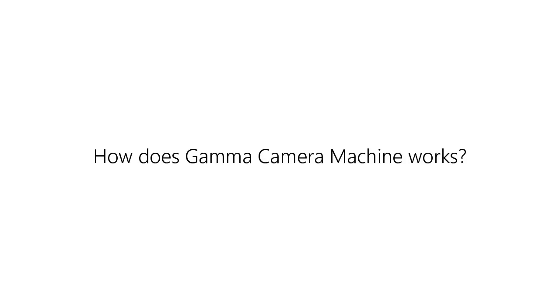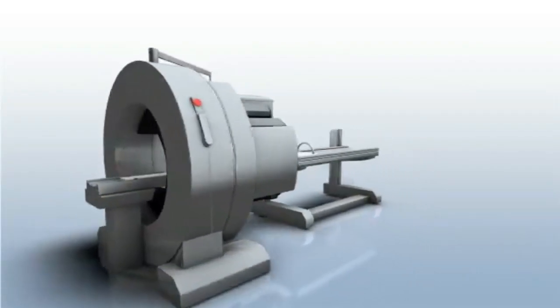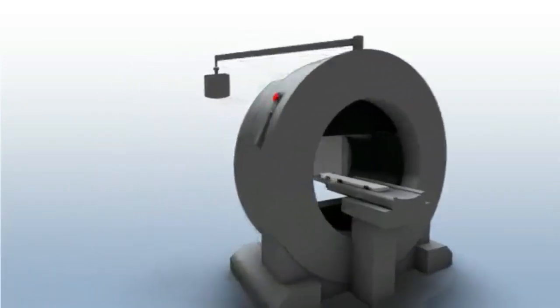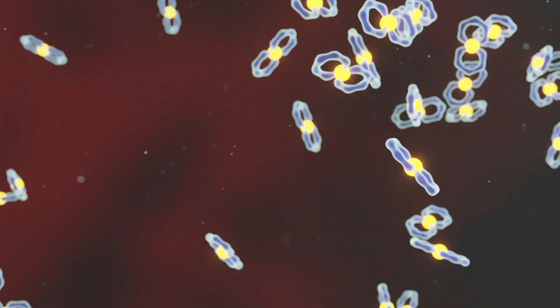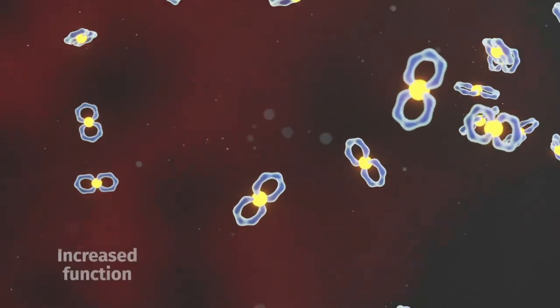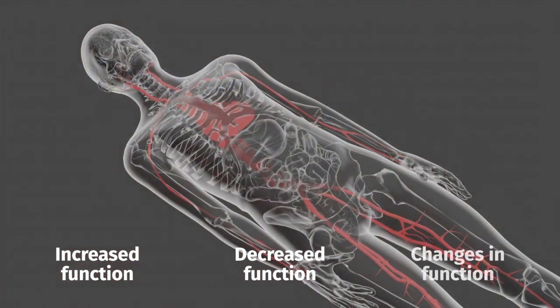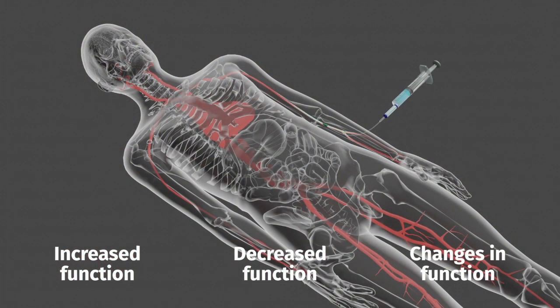How does a gamma camera machine work? Gamma cameras, also called Anger cameras and scintillation cameras, are the most common means of forming an image. These cameras capture photons and convert them to light and then to a voltage signal. This signal is reconstructed to a planar image that shows the distribution of the radionuclide in the patient.